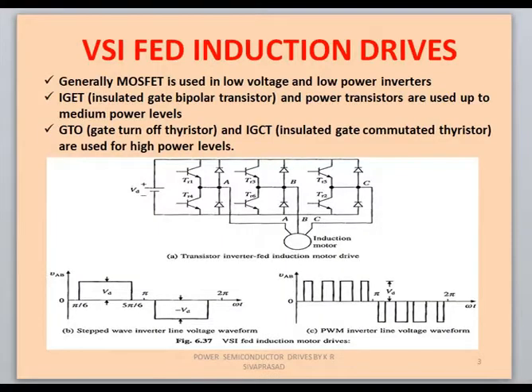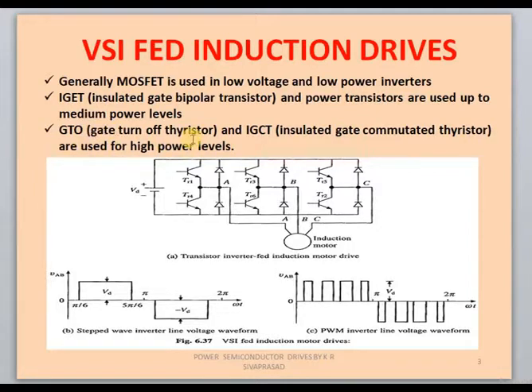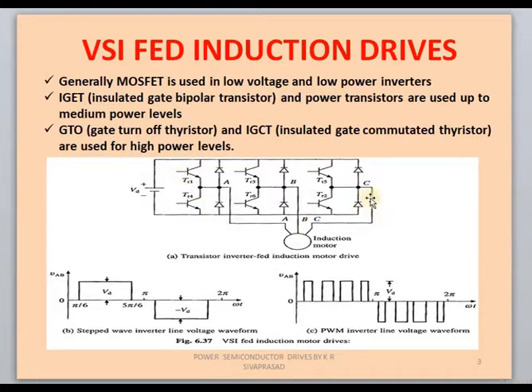We use the basic circuit diagram of the voltage source inverter. You can use different types of devices depending upon the power rating requirement. For high power rating you can use GTO or IGCT — IGCT is insulated gate commutated thyristor, and GTO is gate turn-off thyristor. For medium power applications we can use IGBT (insulated gate bipolar transistors), and power transistors. For low power applications you can use MOSFETs.